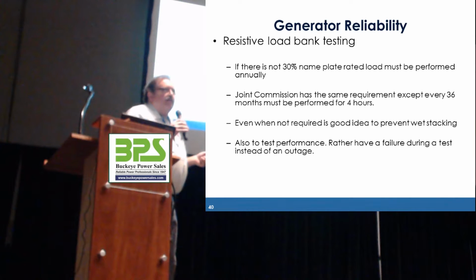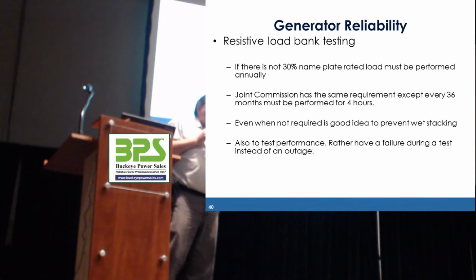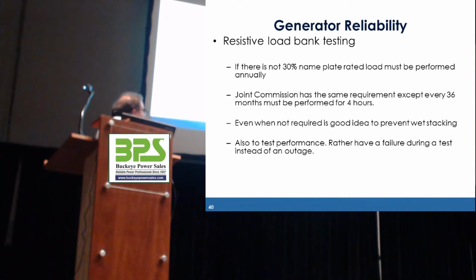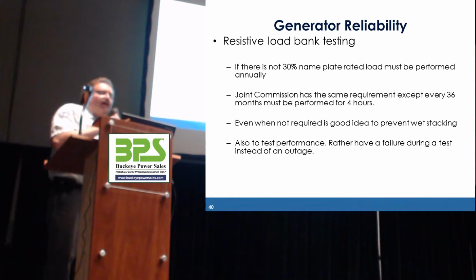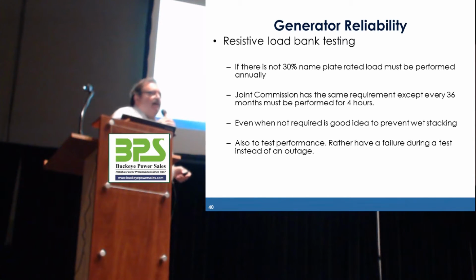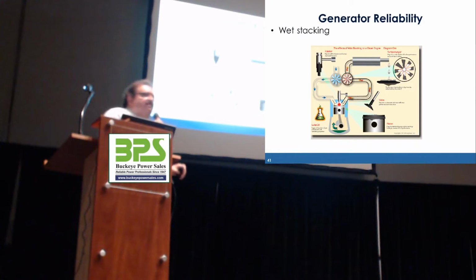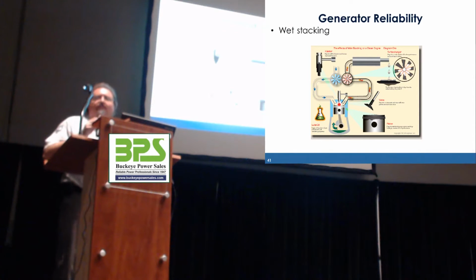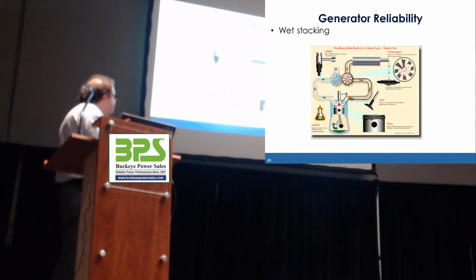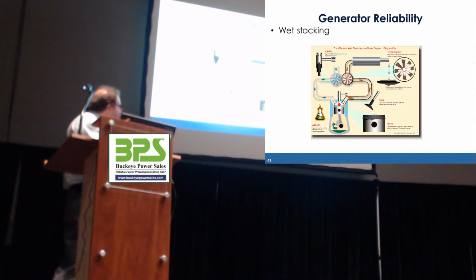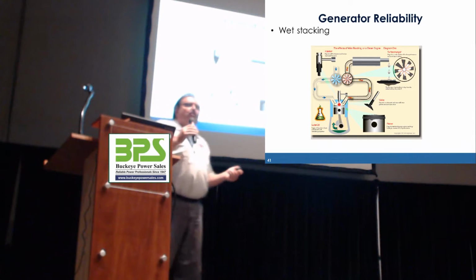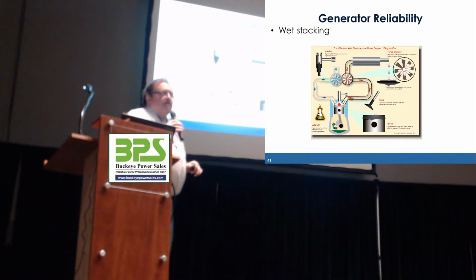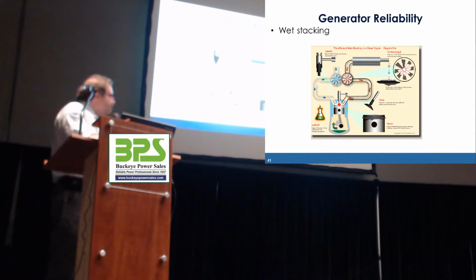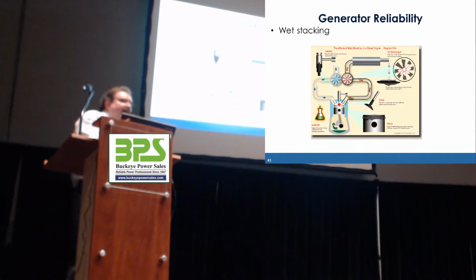And that's what this is all about. This is all about when a machine is lightly loaded, we get a concept called wet stacking. And basically what wet stacking is, the machine doesn't burn all the fuel that's injected into the cylinder. So it builds up as carbon on the pistons and the valves and the injector tips. So you lose horsepower, you lose performance. The load bank test takes and blows all that stuff out.